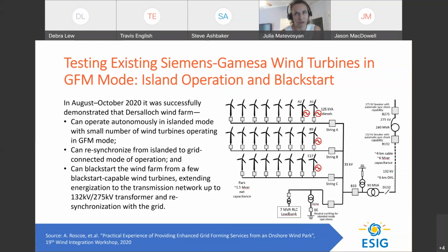They actually went all the way down to 1 wind turbine in grid forming mode, but said that they were able to reach stable operation with 2 wind turbines operating in grid forming mode. They also tried connecting a 7 megawatt load bank to the island, powering up the island with some load in it, and were also successful with that. Then to do black start, they equipped 4 wind turbines with small diesel generators, 125 kVA each. Just to put it into perspective, the turbines are 3.4 megawatts. They could have done this with a battery as well, but diesel was faster to test, and that was just a proof of concept, that it's possible.